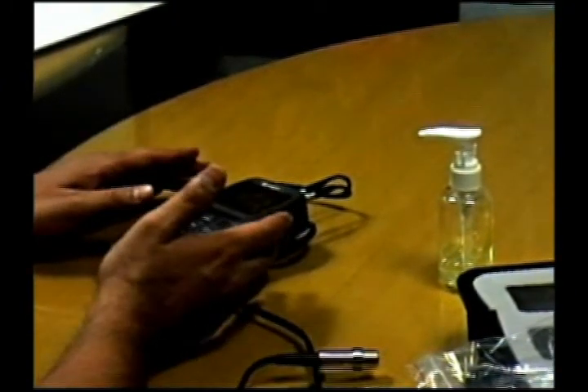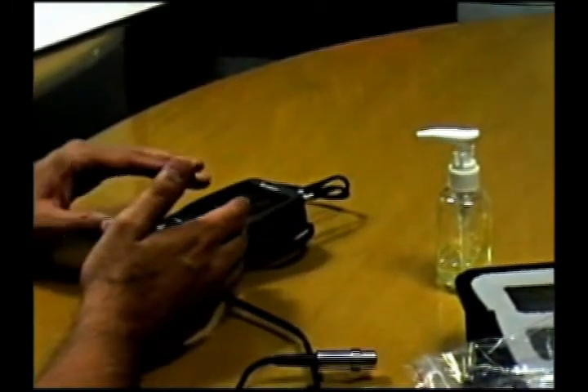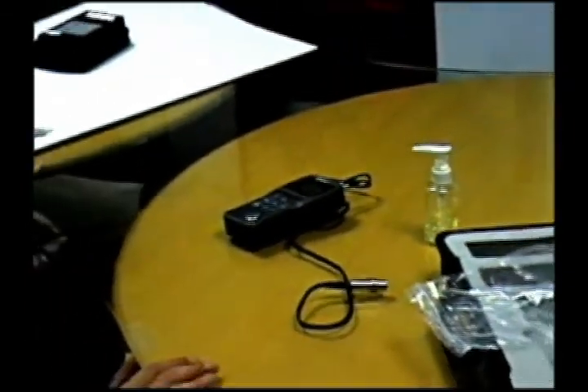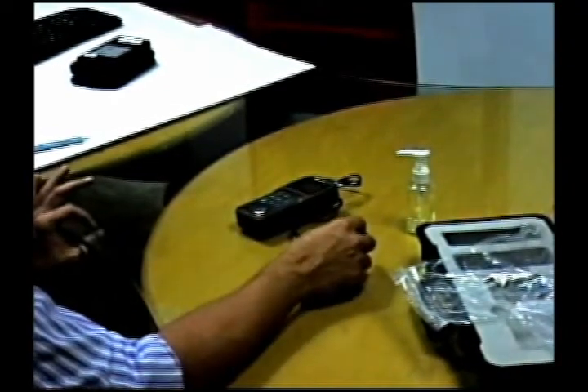As I mentioned, there are two ways that you can utilize the instrument: by calibrating the instrument on the known thickness or a known velocity. Once again, as I start, we know that we have one known thickness of 12.98 millimeters.